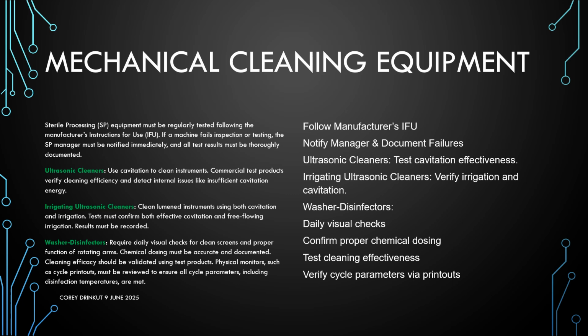The washer disinfectors, we run a test in them every day to make sure that it is doing its job. You need to make sure that the chemicals are filled for the washers. You want to make sure that the piping, the line that leads from the chemicals to the washers, is actually pumping the chemicals. Because if it's not doing its job, if we have a clogged line, we gotta get that fixed.